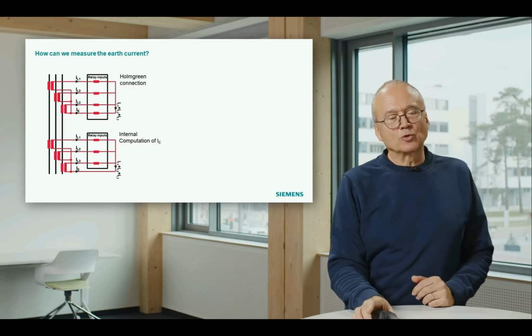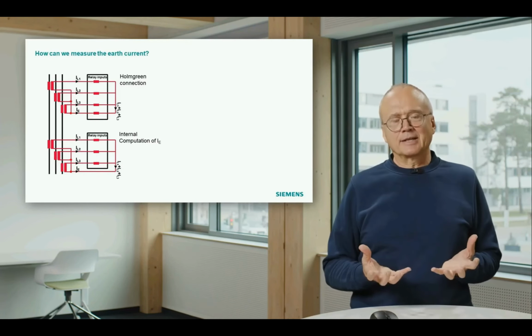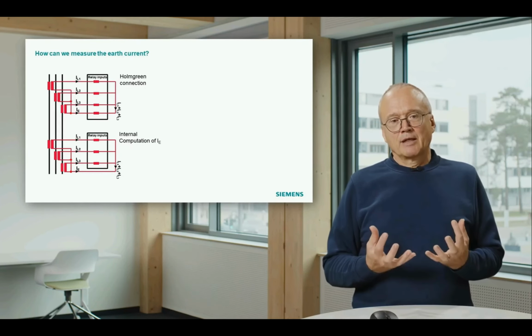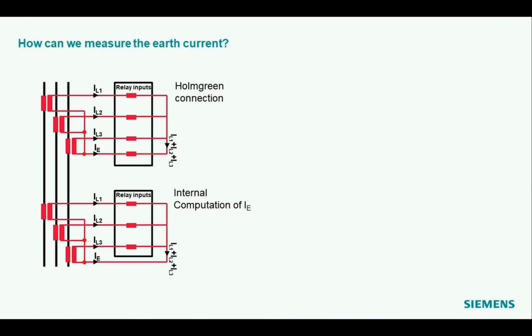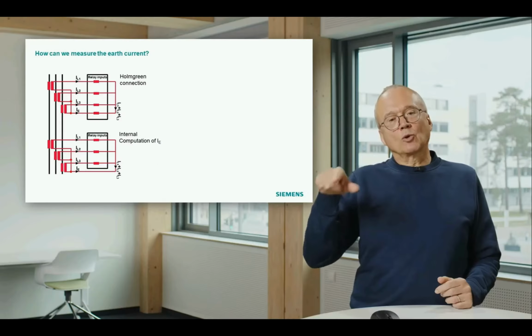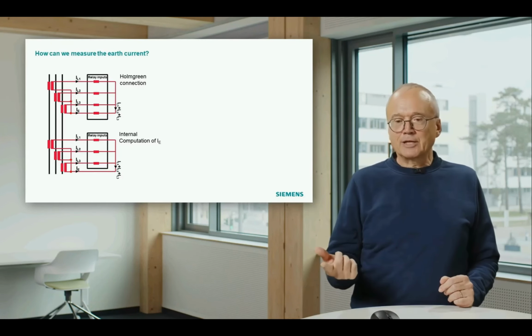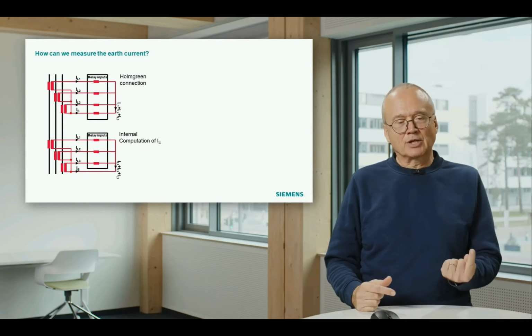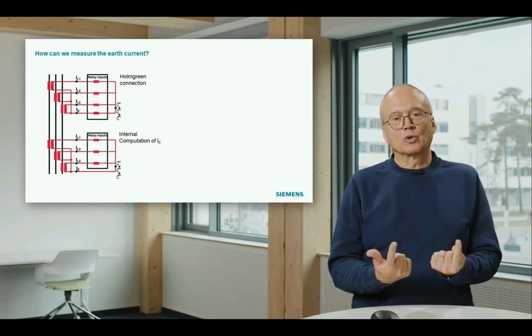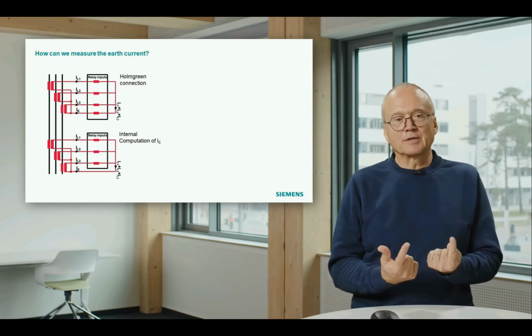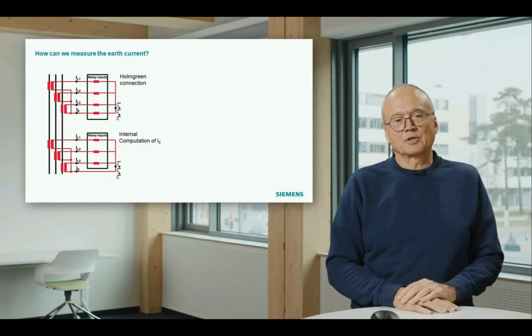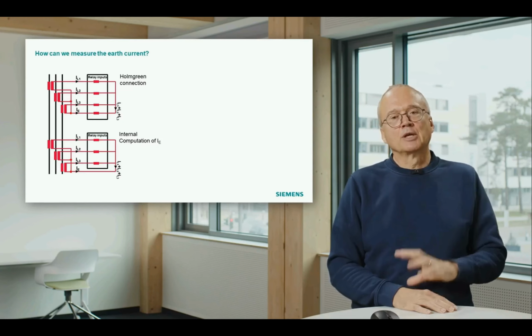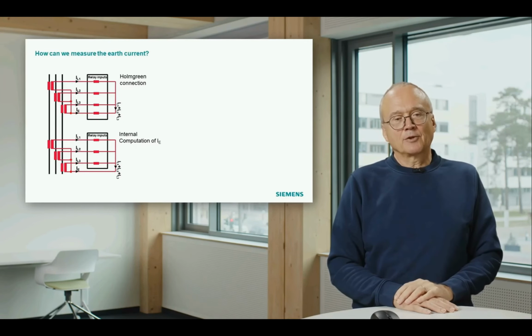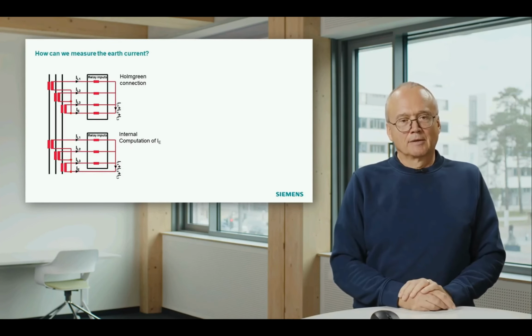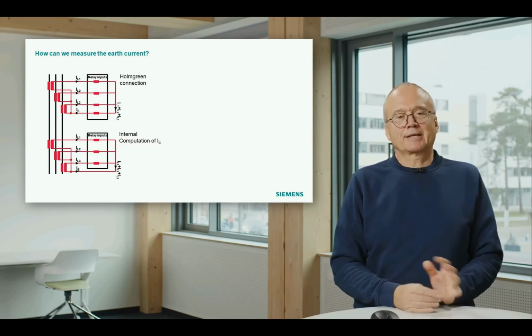The advantage of the Holmgreen connection is that you have a certain amount of redundancy in your data acquisition. You can measure the earth current by using this 4th measuring input to measure the sum of the 3 currents, and you can also do the computation internally, and then you can check: is the earth current you measure identical with the earth current you compute? If you see a significant difference, it is an indication that something is wrong in your data acquisition. With this 4th measuring input, you get an additional redundancy in the measurement, and you can block the system if you detect something.